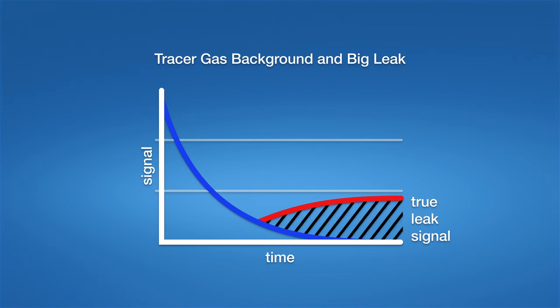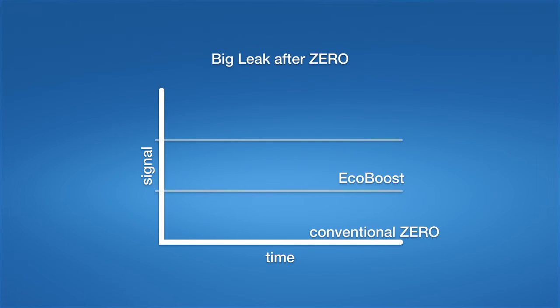The new inficon EcoBoost is able to predict the natural background. All it needs to work correctly are two seconds of the decreasing blue curve before pressing EcoBoost. As a result, the new EcoBoost will show the true leak size instead of an unknown fraction of it. This was in case of a rather big leak.